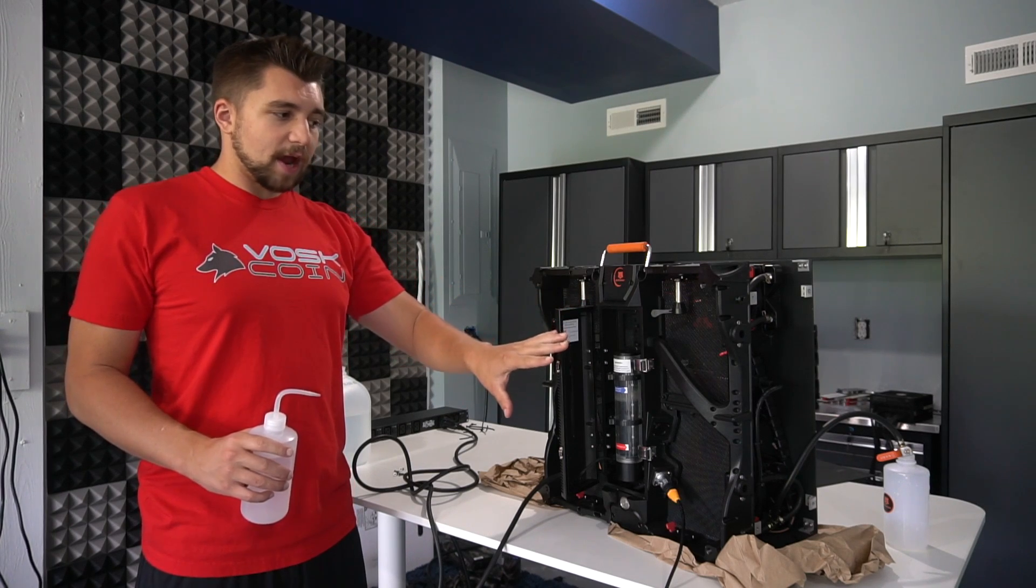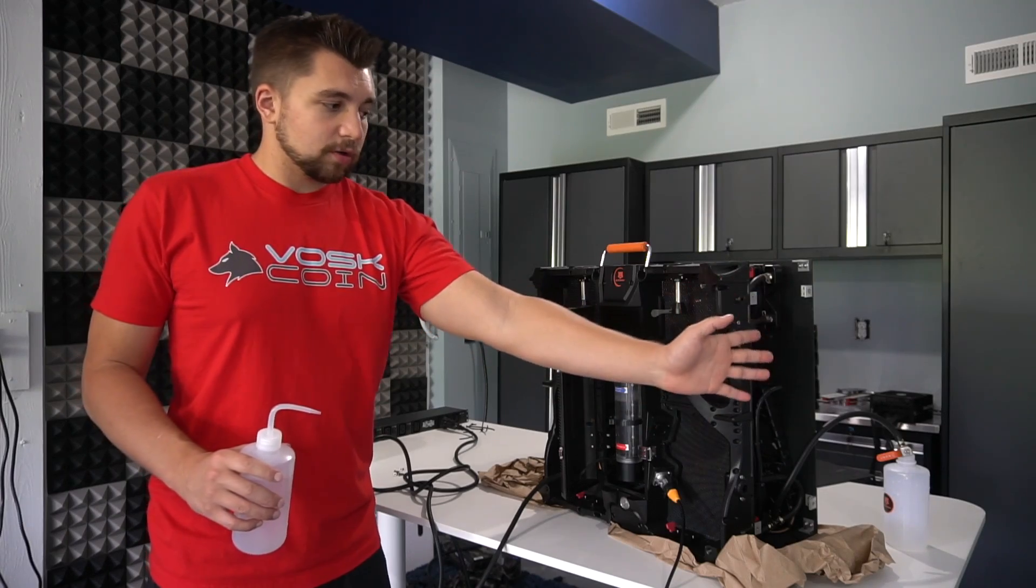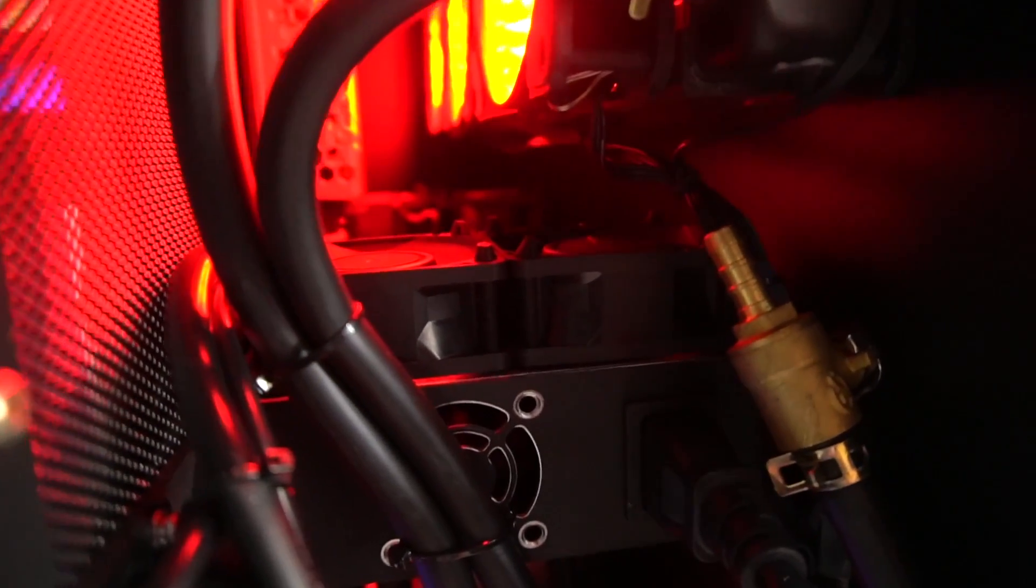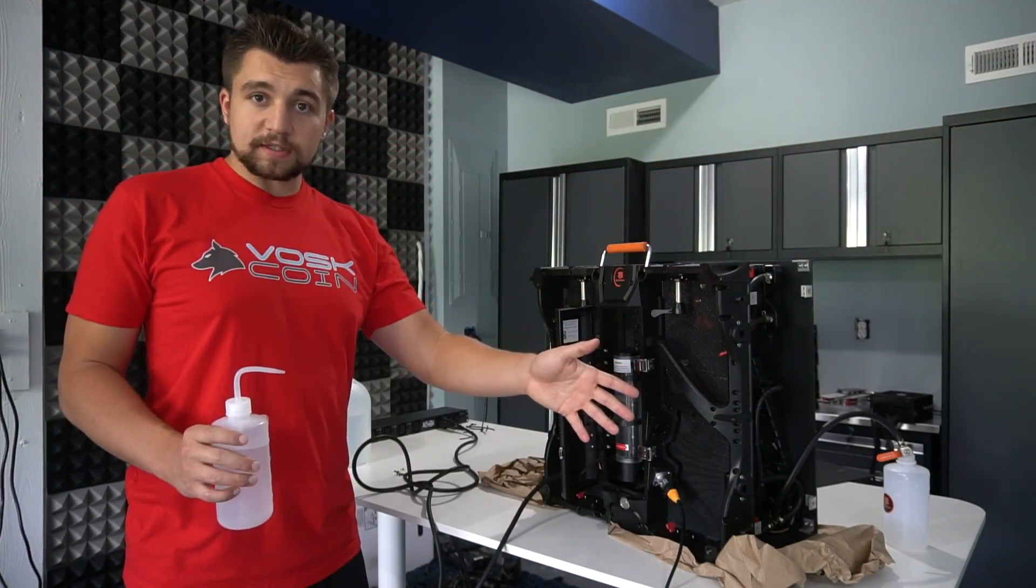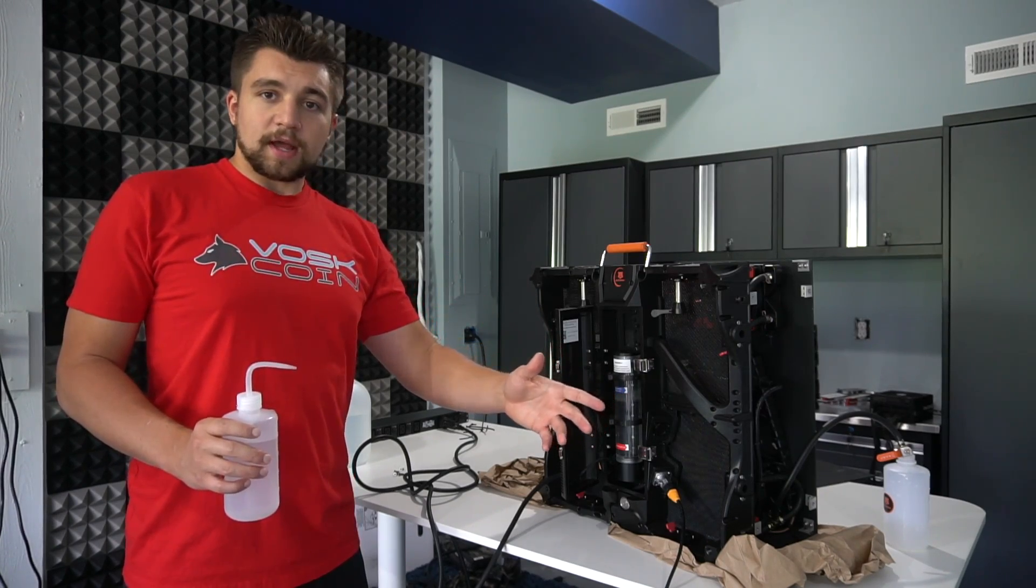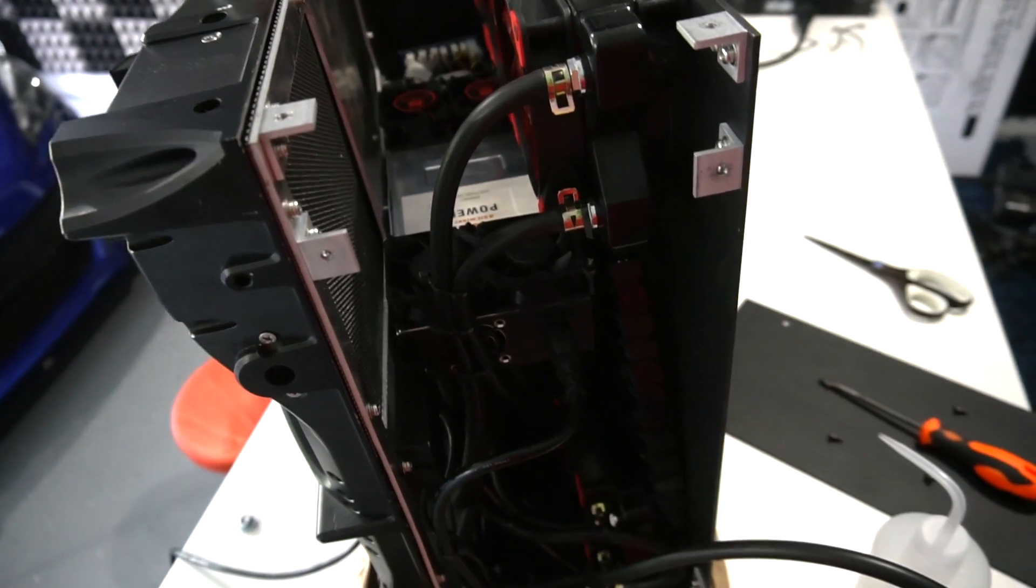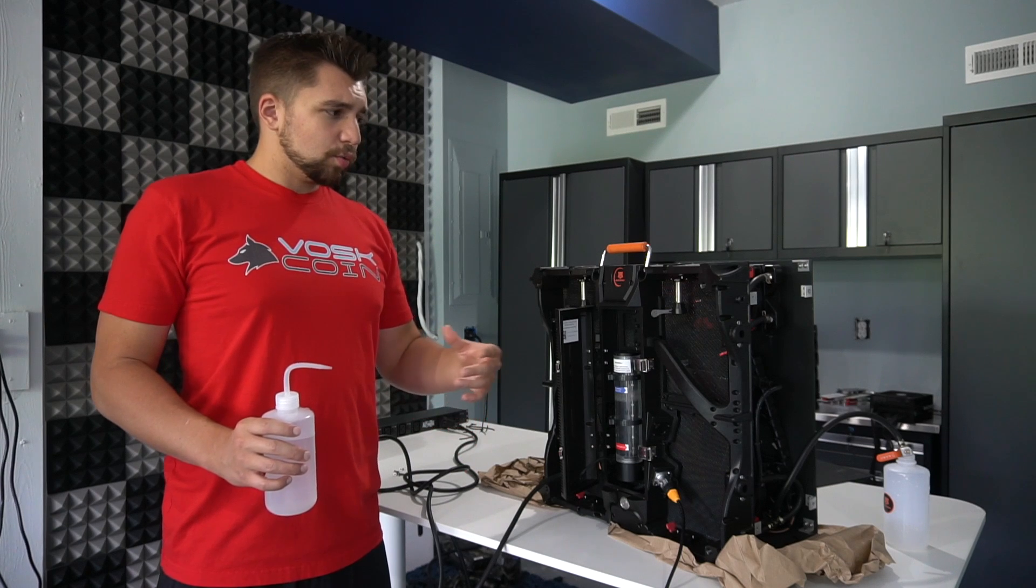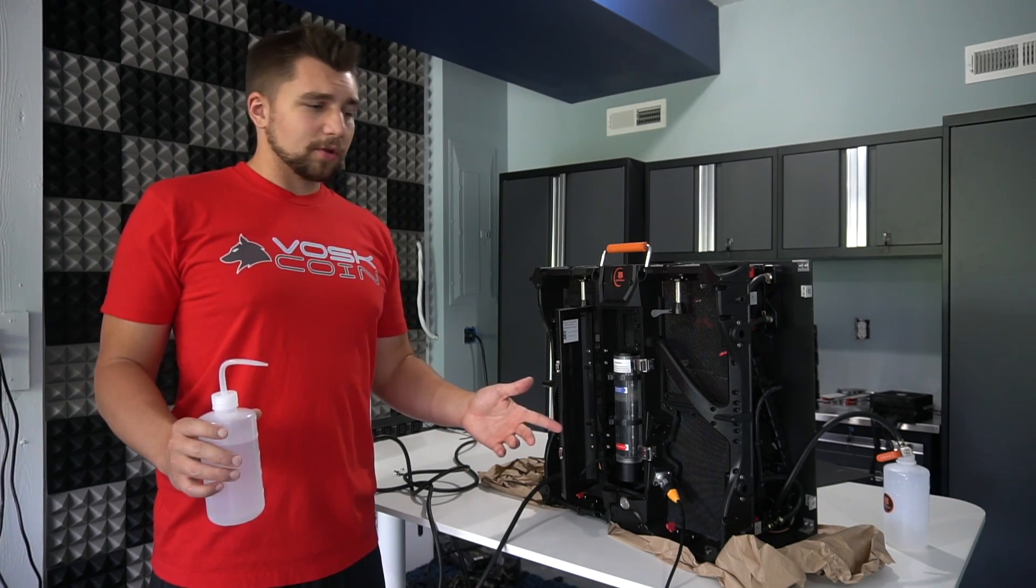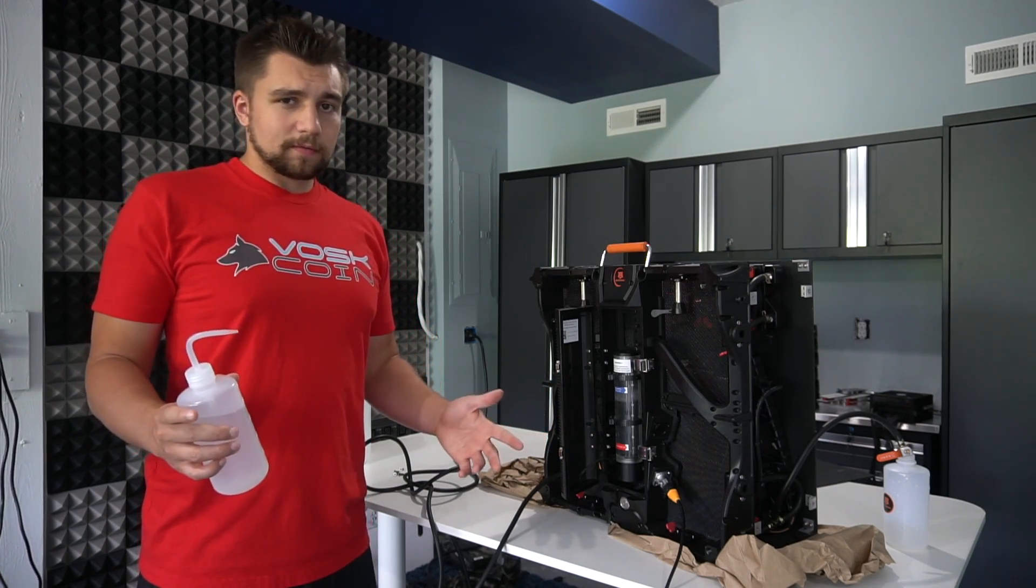Then you're going to open the side of it. So if you're looking at the back of the unit and this is where the water cooling reservoir is, that's the back of the unit. On the right side, if you're looking at it from the back, is where you're going to take the panel off. And then you're going to cut a couple of zip ties and this will allow you to release this lever. And this is what's going to drain liquid out of the system. And you need to drain liquid initially to make sure you get all the air out of the system because naturally there's going to be air in these lines.